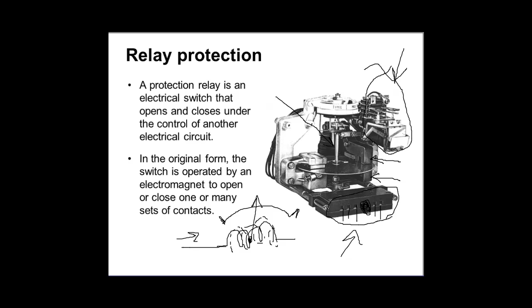And that's enough to send a trip signal from a DC source, which happens to be a battery, to a circuit breaker. By the way, what is on top of this relay, this bit? That's the time setting. So the time setting is on the top and the current setting is at the bottom, and you have a disk which is under the influence of the torque, which is a combination of current setting and time setting. And when the disk starts to move, the auxiliary contacts change position.